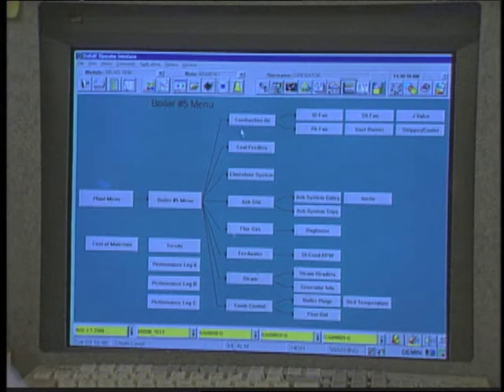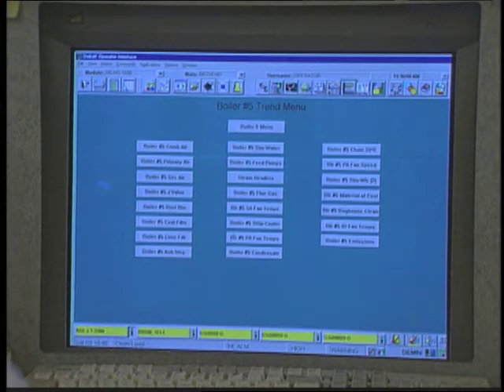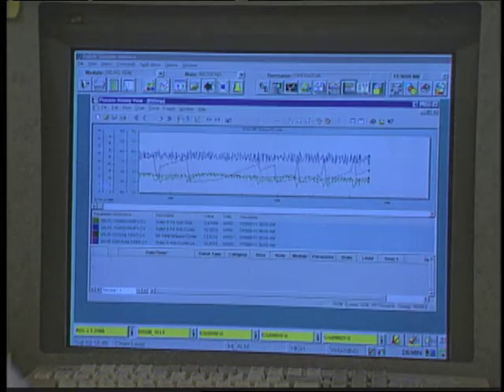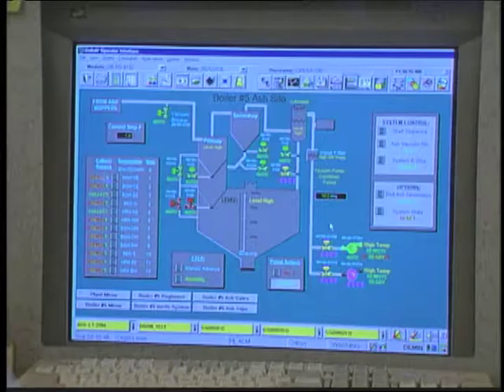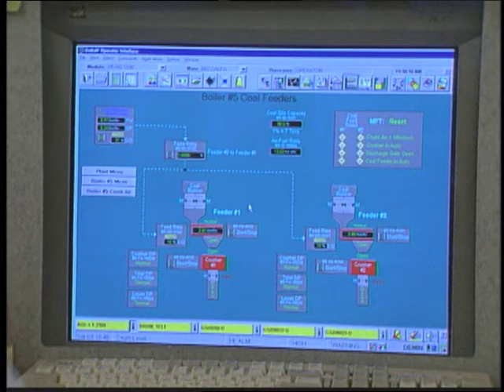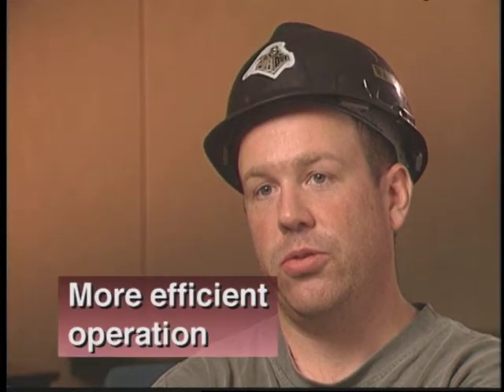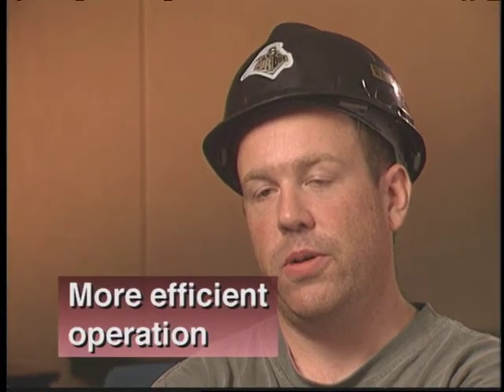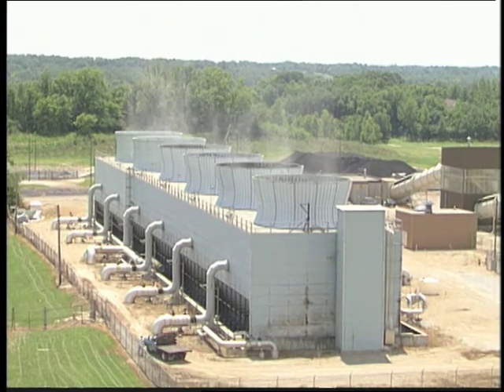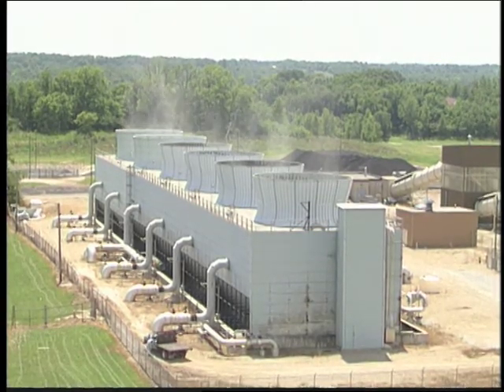My ash system, I'm not stripping more than I need to, right? I can be a lot more efficient. I'm not wearing out those pumps and stuff like that because I can look for the last 24 hours, last week, last month, and see how often we're doing that, right? That's a big plus. And then it really helps us control the tower that we use for our chillers and for our generator. Helps us control the chemicals in that tower. We can see exactly how often we're blowing that tower down. We can trend the TDS, total dissolved solids, in that tower, and we can tighten up a lot of our systems that way. I look at the trends every hour on the hour.